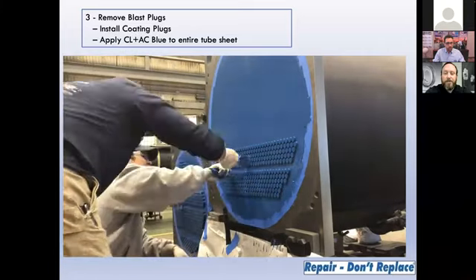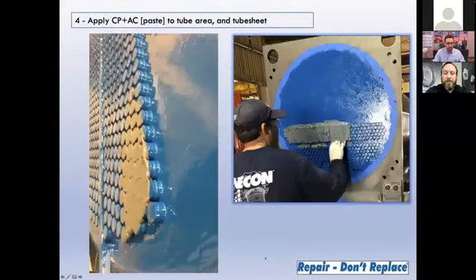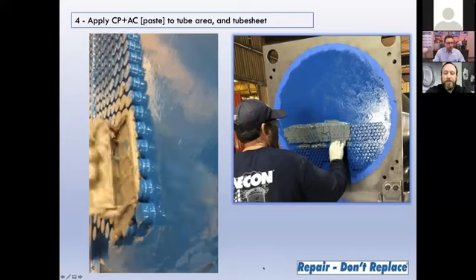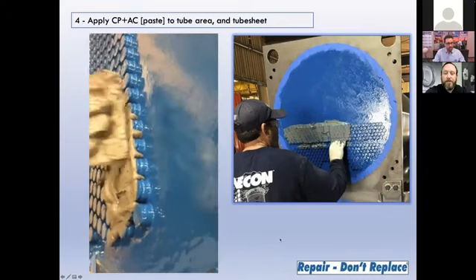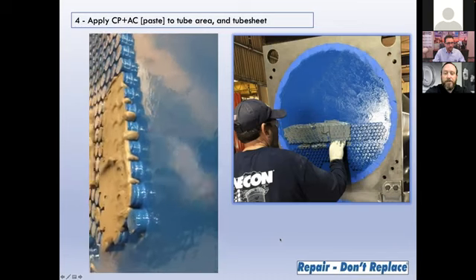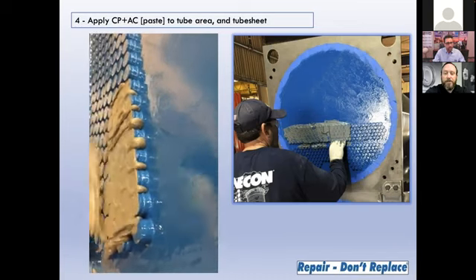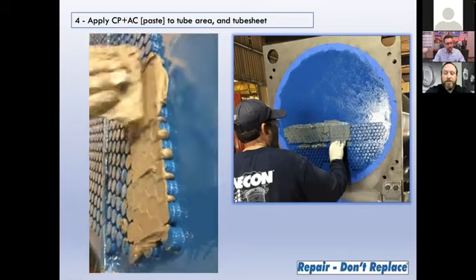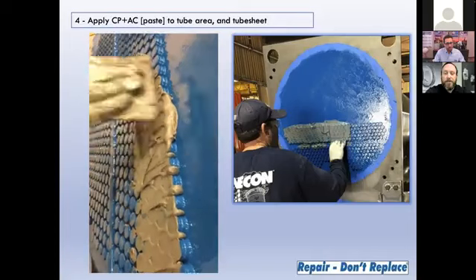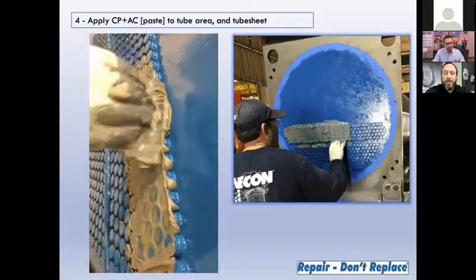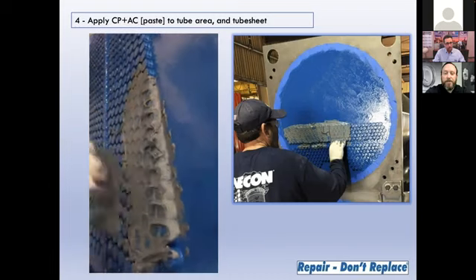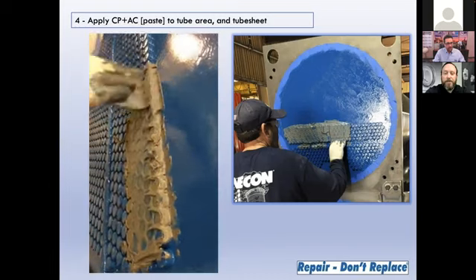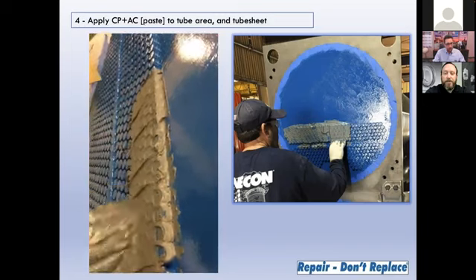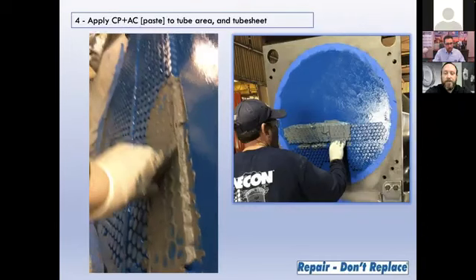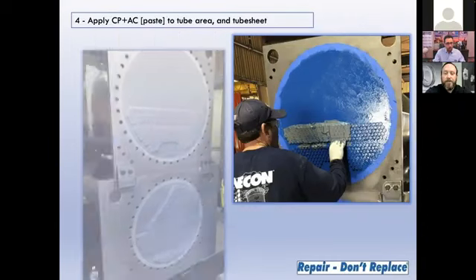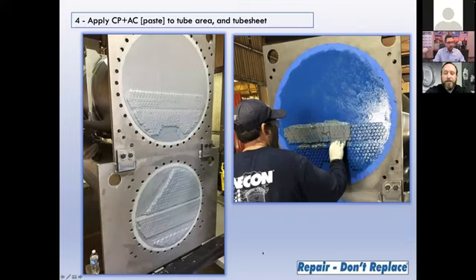The next part of the process is to apply the CP Plus AC to the tube sheet surfaces. In this video, you'll see that the CP Plus AC is pressed firmly in a vertical fashion, pressing down in between the tubes, getting intimate contact between the tube sheet and the tubes and the CP Plus AC, pressing firmly, going vertically, then horizontally, making sure we get all the possible air out of the system as we're pressing down. What we're trying to do is maximize the amount of product we use and make sure we don't overbuild on top of the plugs too often or too much. We will allow the product to cure overnight.